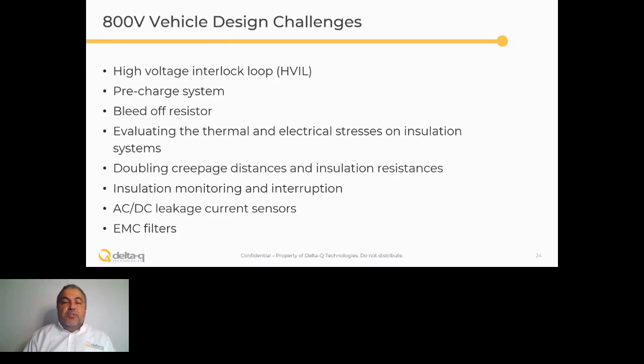One of the major challenges in these systems lies in continuously monitoring insulation faults or loss of isolation, then providing early interruption. The causes of such insulation faults in normal operation can be, for example, contamination, salt, humidity, faulty connectors, or mechanical influences. Evaluating the thermal and electrical stress on insulation systems, selecting proper insulation material, assessing the compatibility of the materials, and finally testing and analyzing them under real-world conditions are necessary.